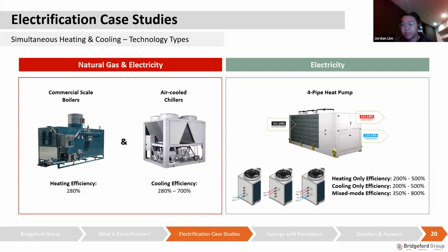I won't dive too much into the details of the efficiency of the air-cooled chillers here. It's actually quite similar to the efficiency of the heat pump. That's a wide range. But for a 4-pipe system, it works better if it's on simultaneous heating and cooling. It can go from 350% to 800%.